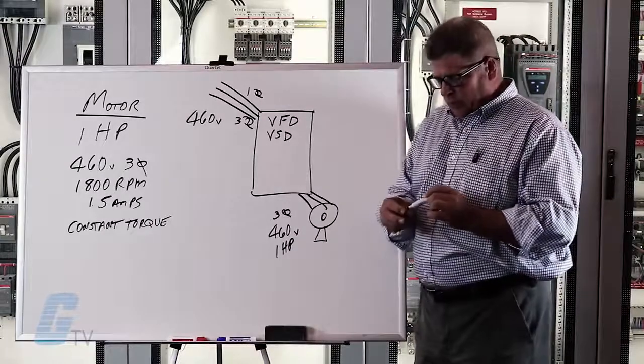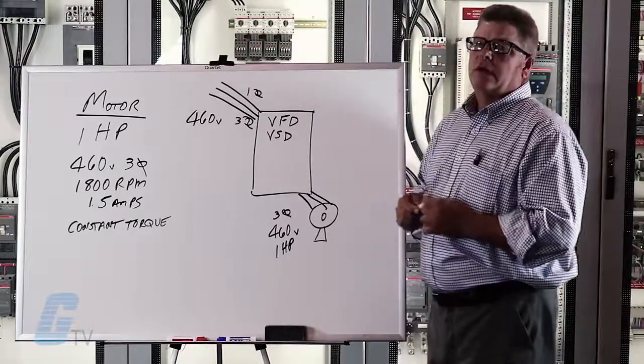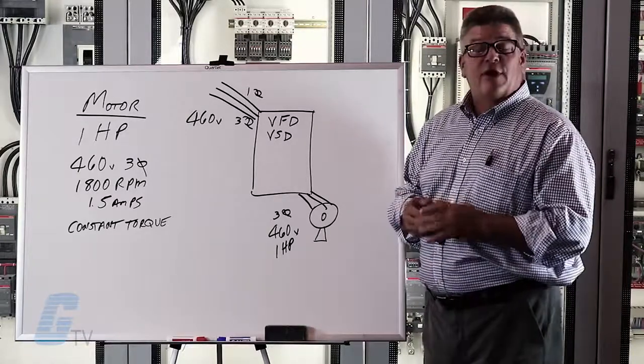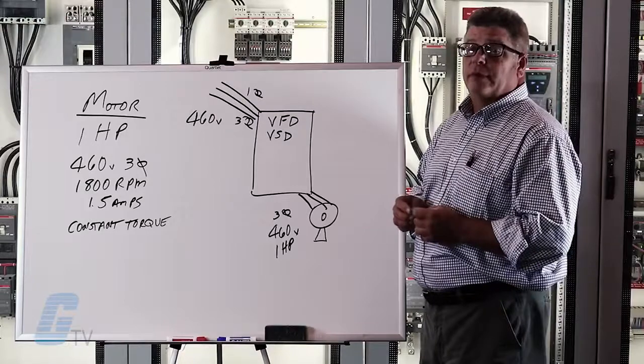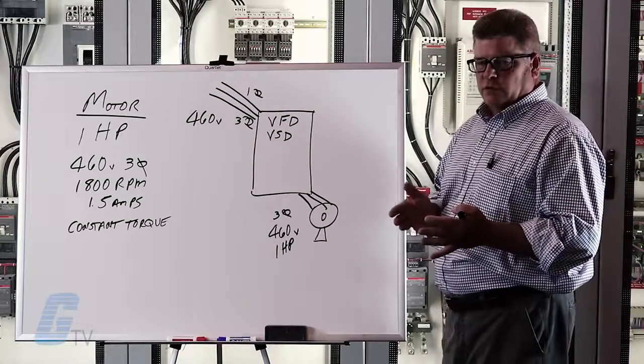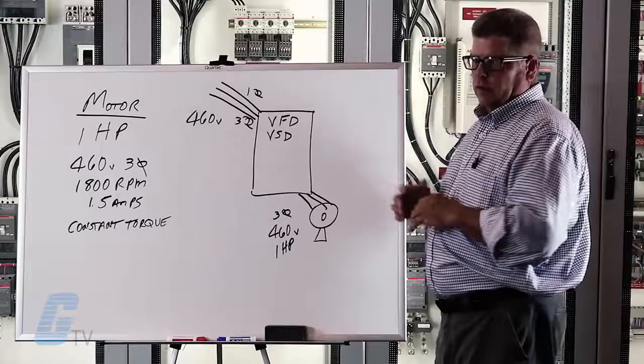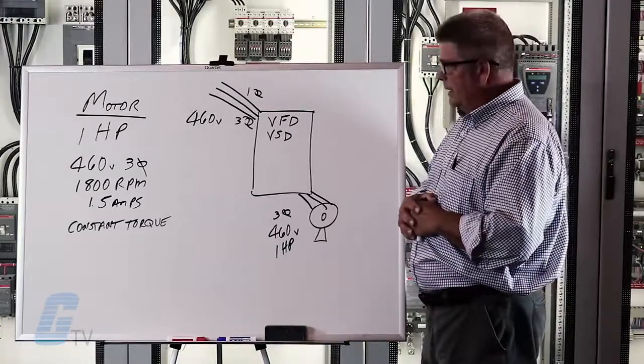Constant torque means that the motor needs to provide its full torque right from zero speed up to its full speed rating. The other option would be a variable torque load like a fan or a pump where you need minimal torque at zero speed and maximum torque at high speed. In our case today it is a constant torque conveyor that we are working on.